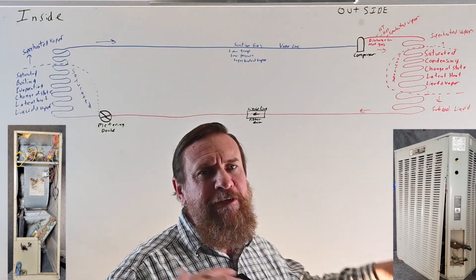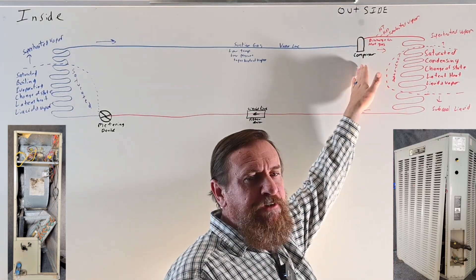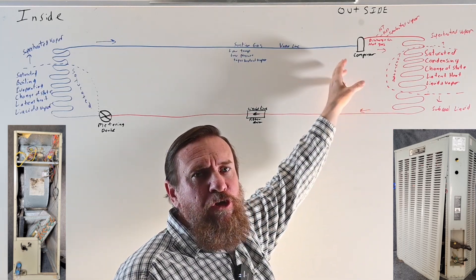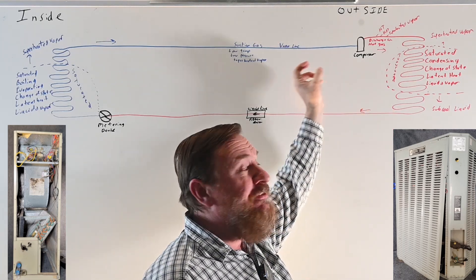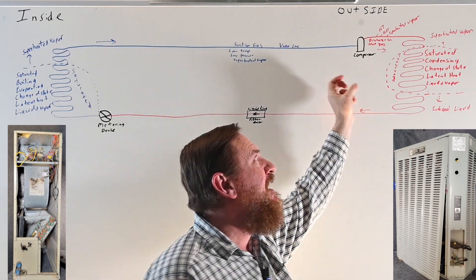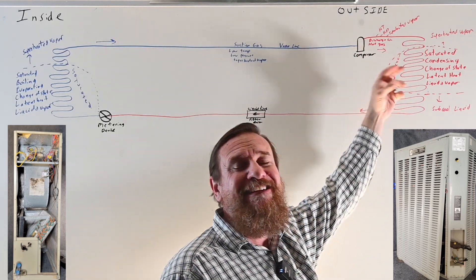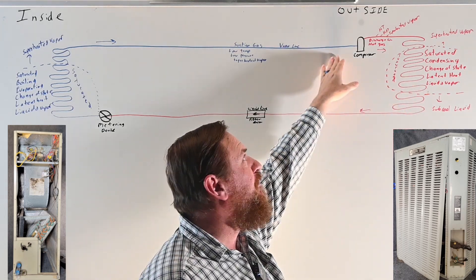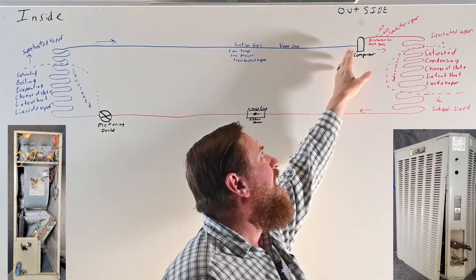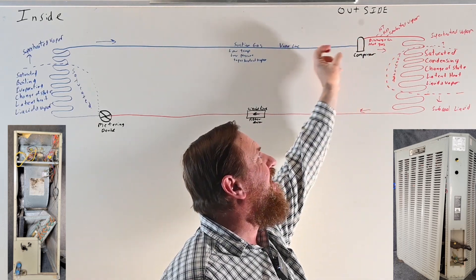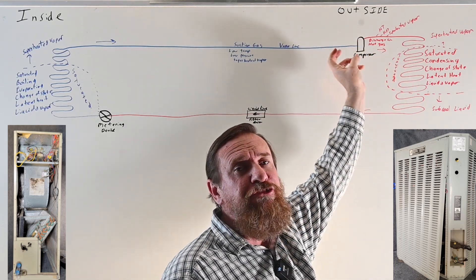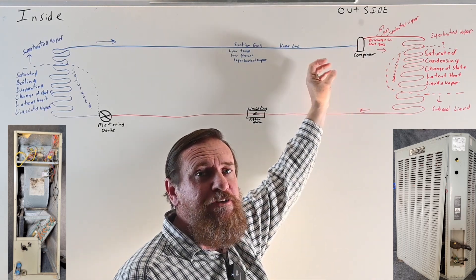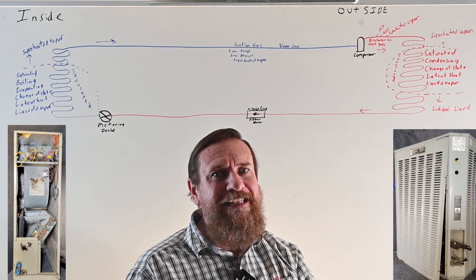Let's take a look at that again from a two-dimensional standpoint. We're going to start from a compressor. We have a low temperature, low pressure, superheated vapor coming in, and high temperature, high pressure, superheated vapor coming out — the discharge line, also known as the hot gas line. Coming in is the suction gas line, a low temperature vapor. That's going to be key later on.